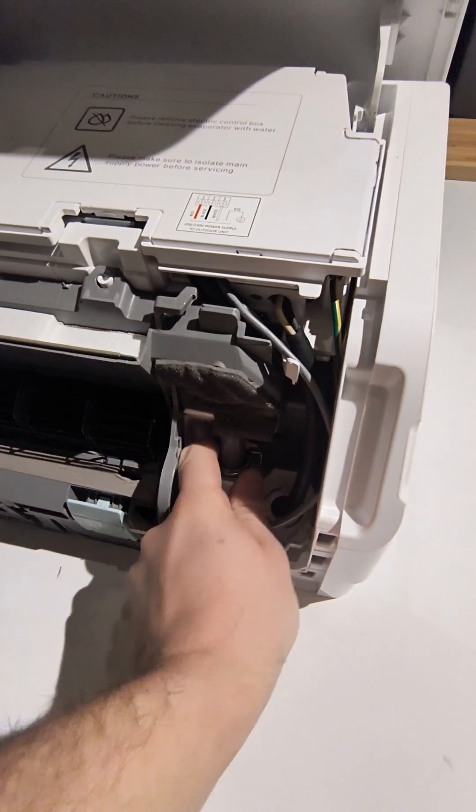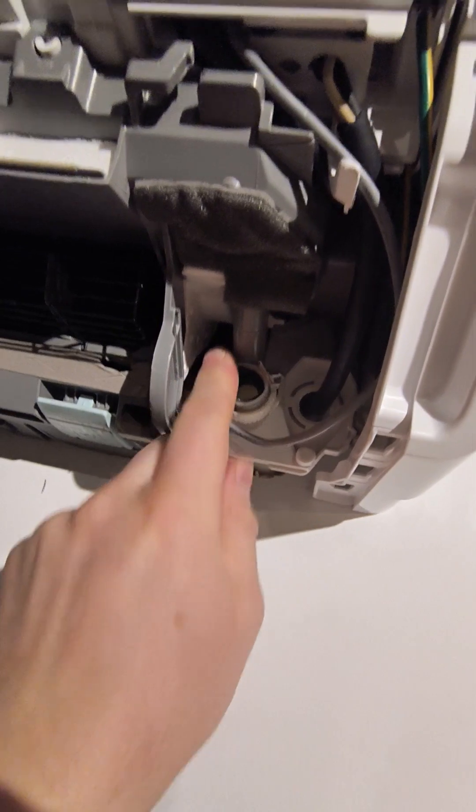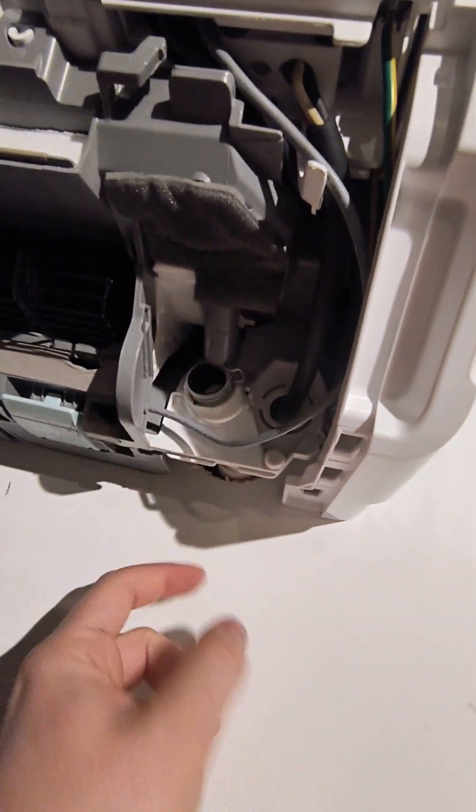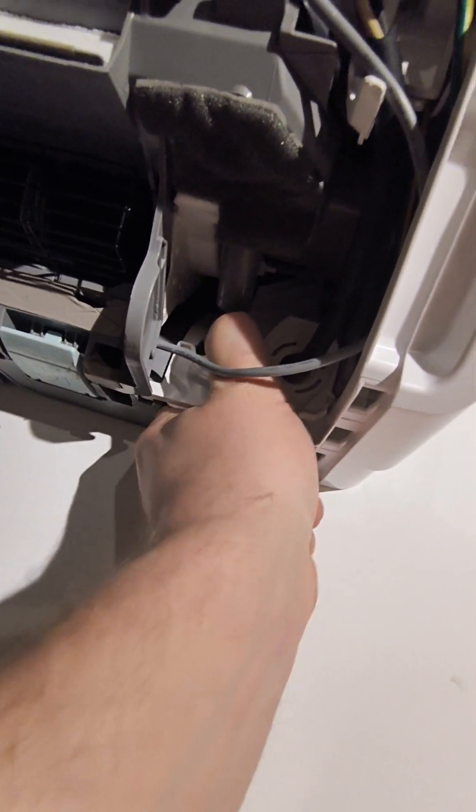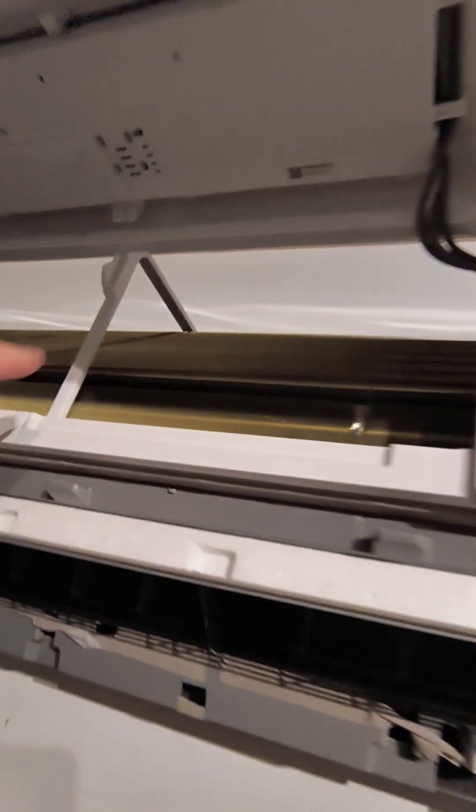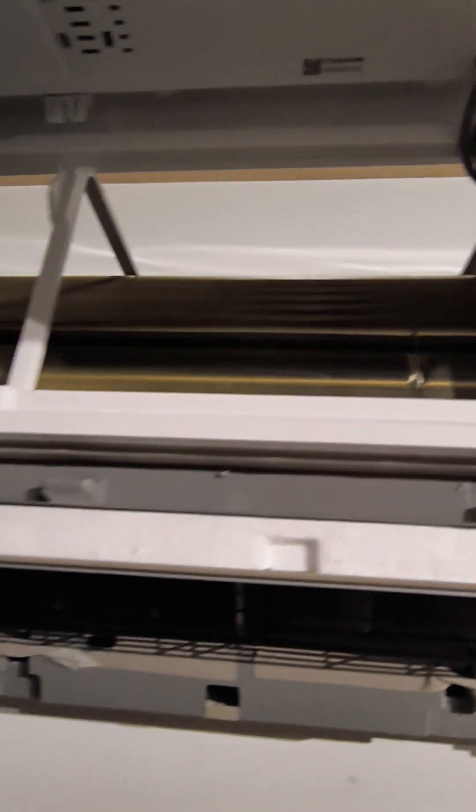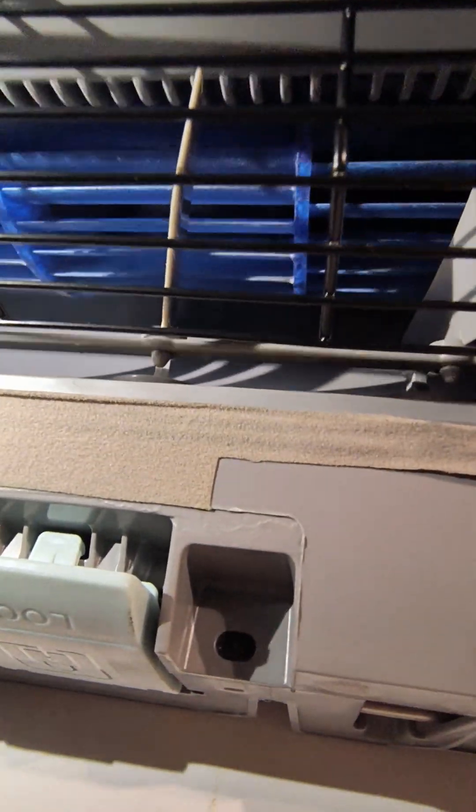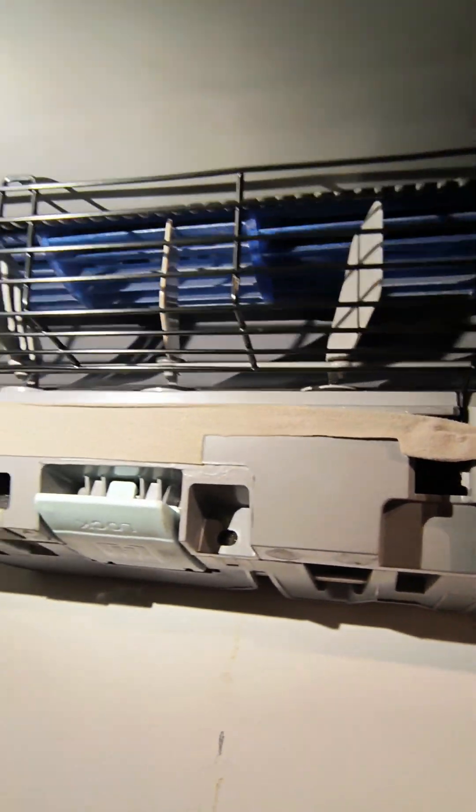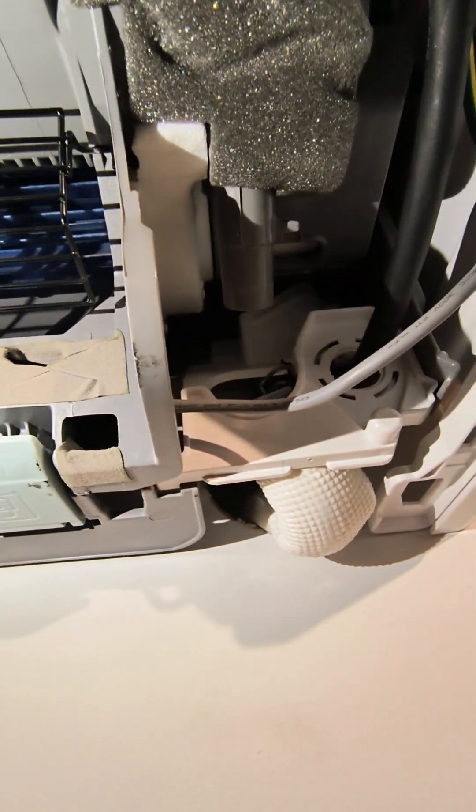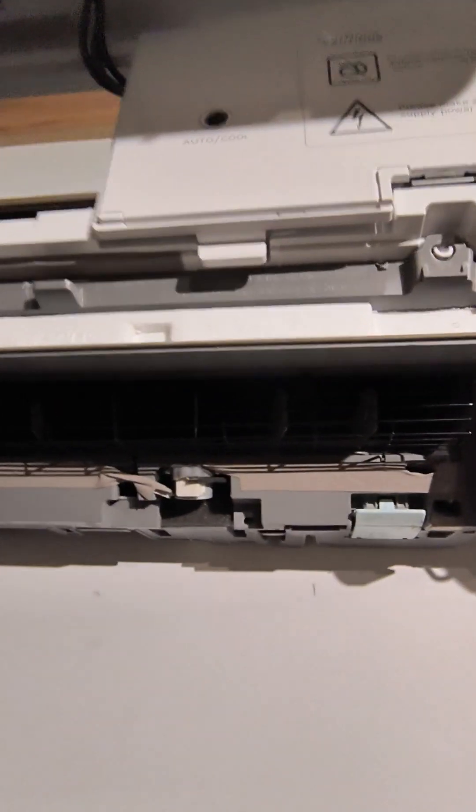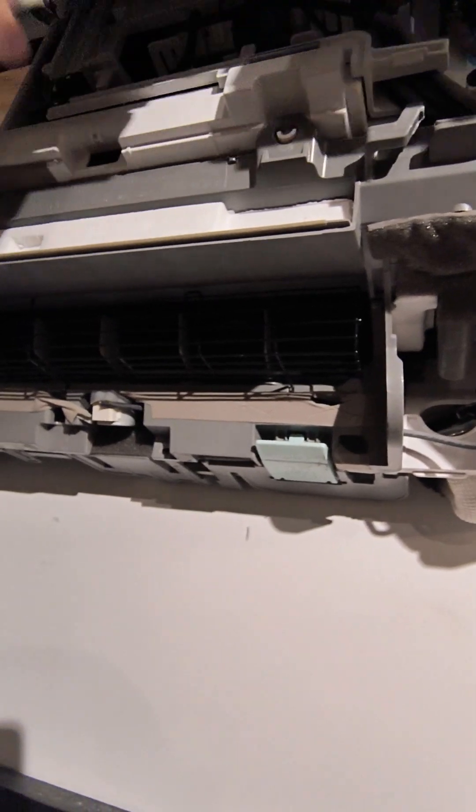Once that drain's popped off you can kind of pop it back in here. It's pretty easy to do the servicing and cleaning on these where we're cleaning the copper coil. But in terms of cleaning that fan up in there, it's very hard if that starts getting nasty. Now that it's stopped we can get a much better look at it. We can see that fan's very clean, as well as the dampers and everything behind it. But if that starts getting too nasty, it's possible to remove this entire assembly which holds the fan motor, this damper, and the whole drain pan.